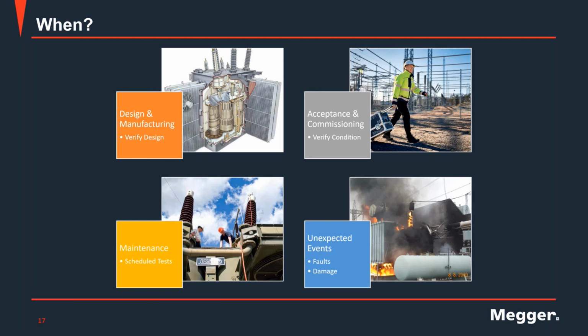And on the last one, obviously, at that point you cannot do TTR, but if you have a fault, a true fault, or any kind of suspected major damage, you perform TTR, and I would say along with insulation assessment. Those are the two main tests that you want to run to make sure you still have a functional transformer, right?